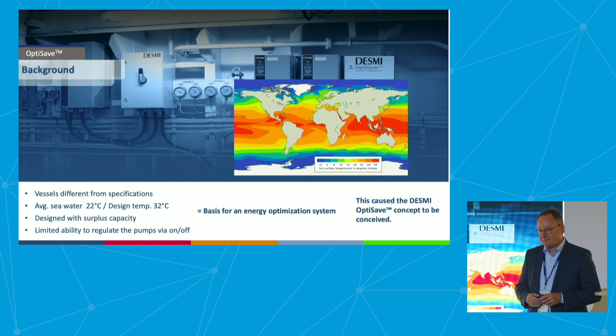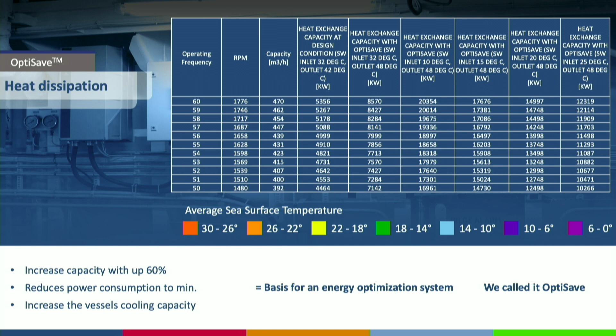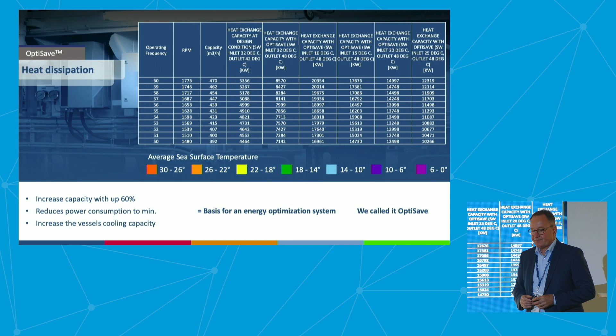Basically, the OptiSave solution is a utilization of what is already installed, namely the heat exchangers for the seawater cooling. Normally, the ship specification is based on a 32 degree inlet temperature and an outlet temperature of 42. We change that, so we are utilizing the delta between 42 and 48 degrees, using the installed equipment to its maximum. The reason we use 48 degrees is that the dew point is 48.5, so we are below the seawater dew point, and hence also operating in the safe area of the installed equipment.